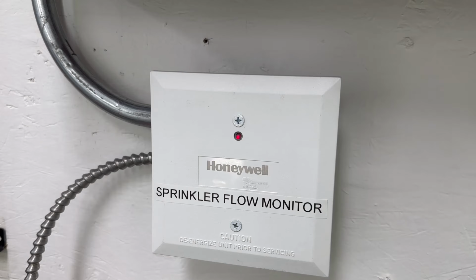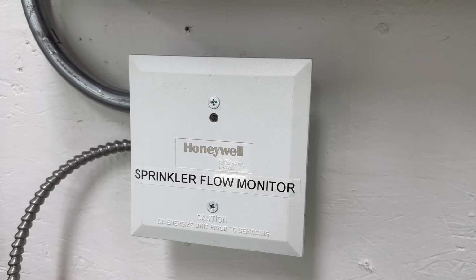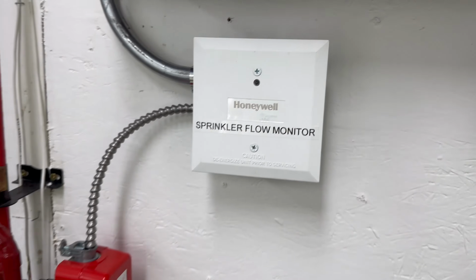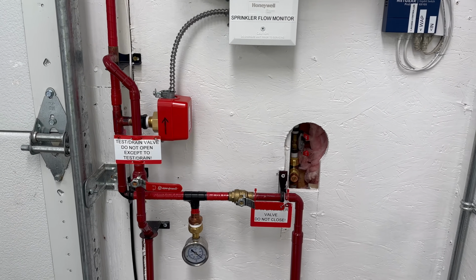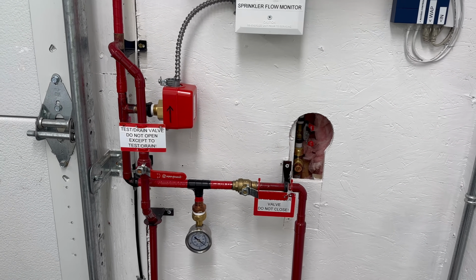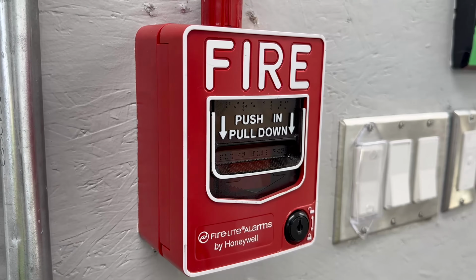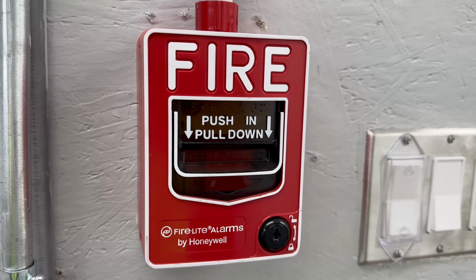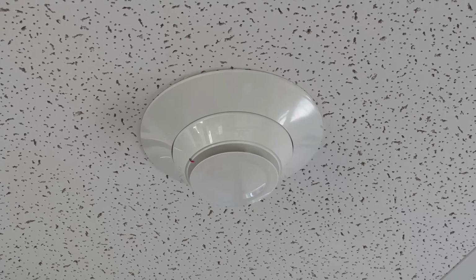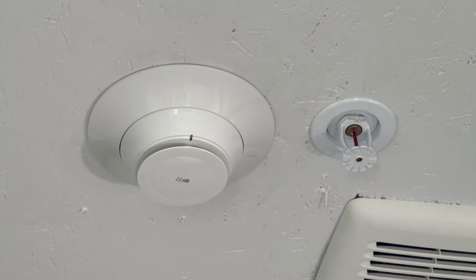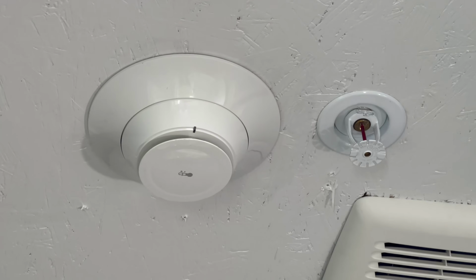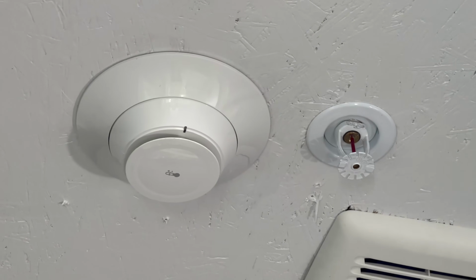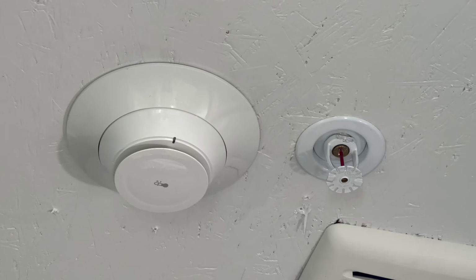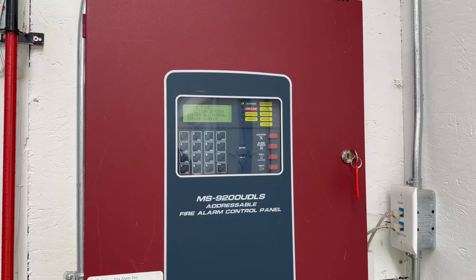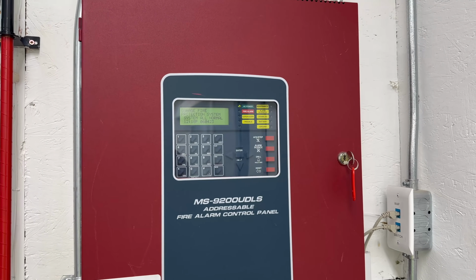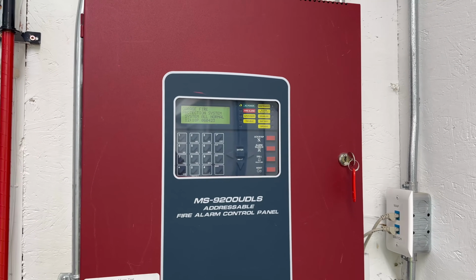That SLC communication loop talks to modules such as this one right here that monitors the sprinkler system for any water flow, meaning a sprinkler head has gone off. However, that same loop will also talk to manual pull stations, as well as the smoke detectors and heat detectors. Every time it blinks, that is known as polling, where the addressable device is communicating its status to the main control panel. Those are known as points, and this fire alarm panel can support up to 198 addressable points.